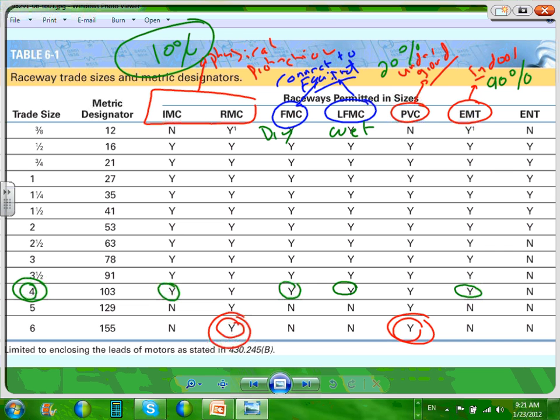So any question about the use of, so there are two types. When we teach this for the apprenticeship, guys, we say there are 2 types of conduits. There is the non-flexible conduits and the flexible conduits. The non-flexible conduits: IMC, rigid metal conduit, EMT. And the flexible conduits are flexible metallic conduit and liquidtight flexible metallic conduits. And there's another one, we call it liquidtight flexible non-metallic conduit. Any question about all these?